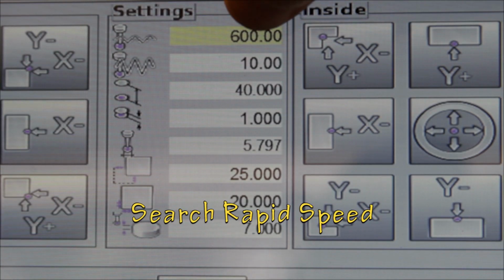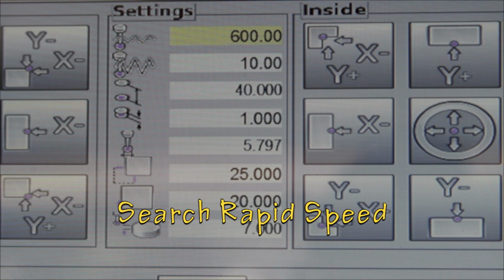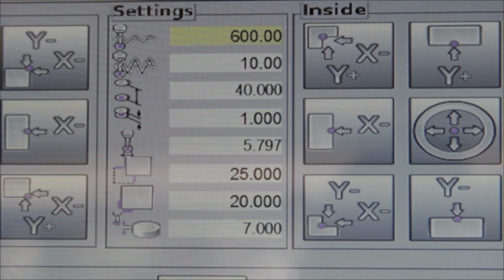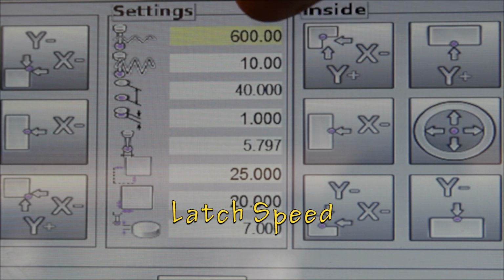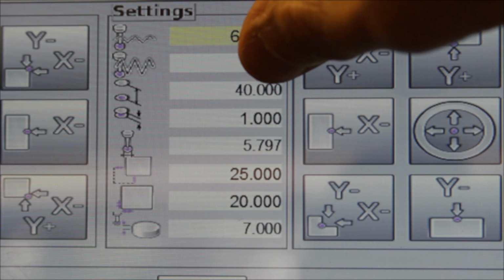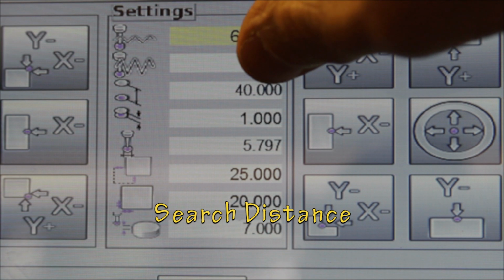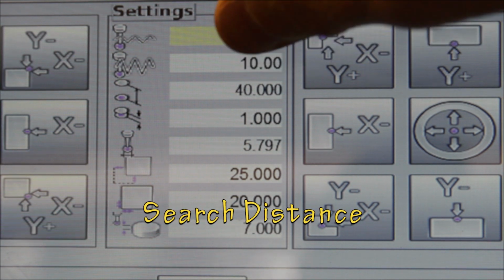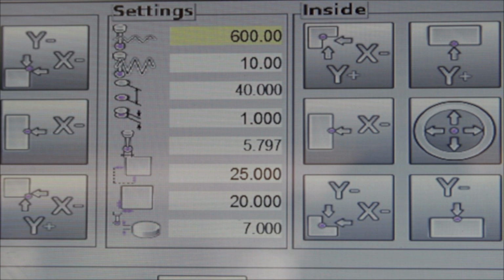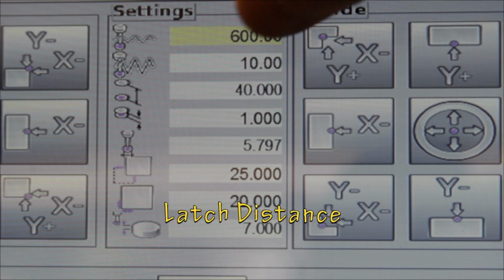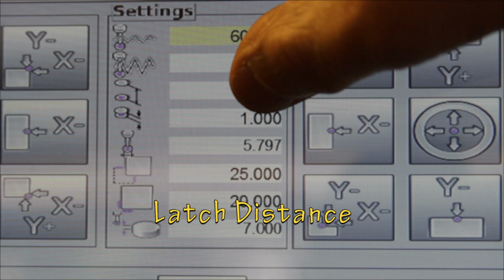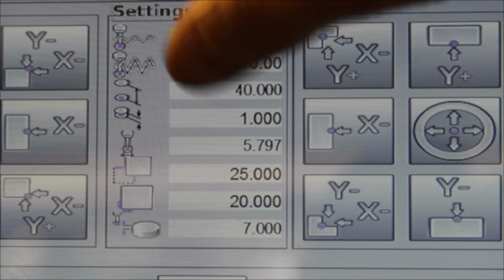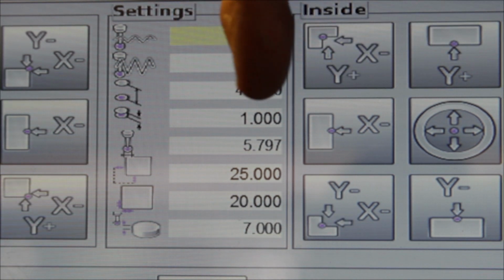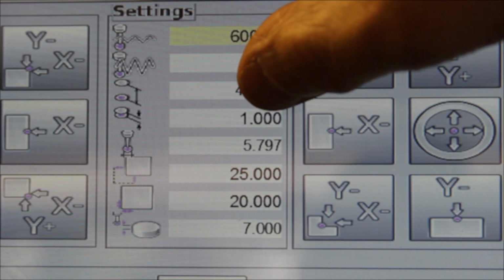From the top, this is the search speed. That's how fast the probe moves when it's traveling fast. Once it's touched the work and come back and then creeps forward, this is how fast it creeps, at 10 millimeters per minute. The 40 is the search distance. That's how far it goes before it triggers an alarm that it didn't touch anything. The latch distance is how far it backs off once it's first made a connection with the part, 1 millimeter in my case.